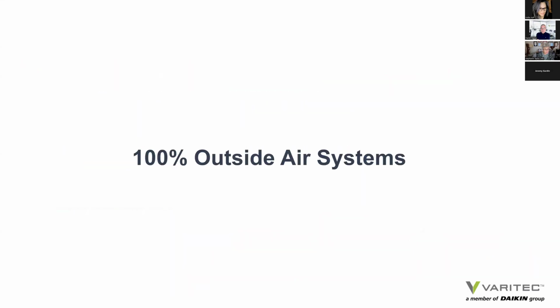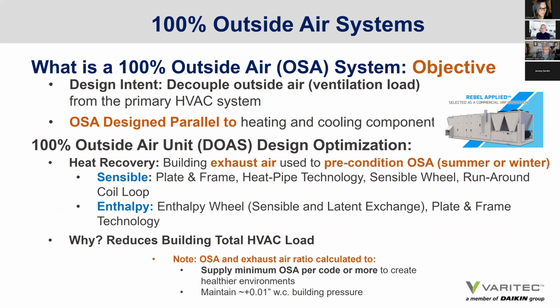Well, let's look at another system that I've spoken to in the past, 100% outside air systems. What is a 100% outside air system? What is the objective? The objective is to decouple the outside air component from the conventional MEP system. We don't want to put an outside air intake into an air handler and allow that outside air to mix with the return air. We're going to condition that outside air independently of the mechanical system, so it's designed in parallel. The advantage of doing that is that we can apply heat recovery strategies that can easily result in a reduction of 25% of the outside air load, depending on whether you're using sensible heat recovery or enthalpy heat recovery.